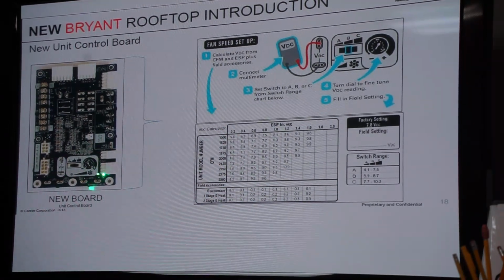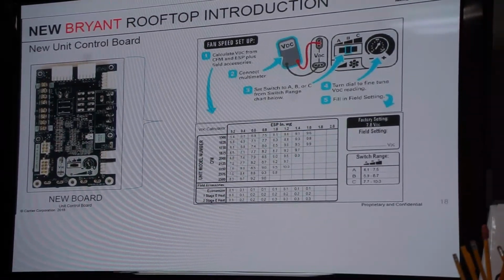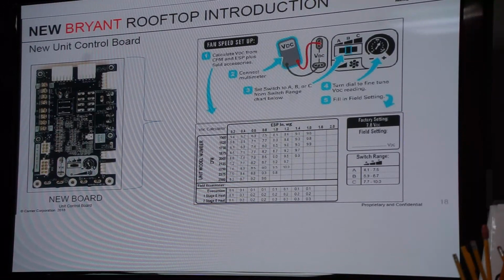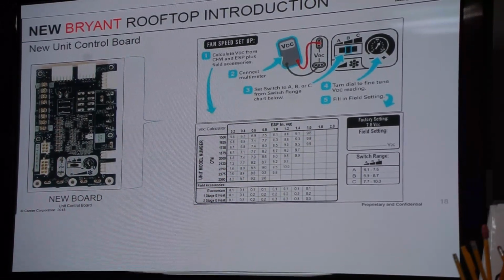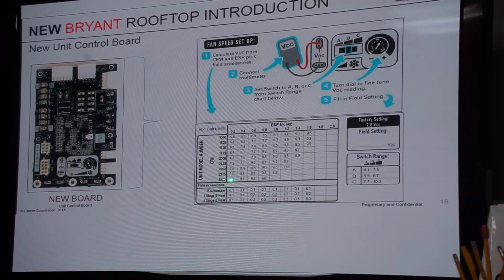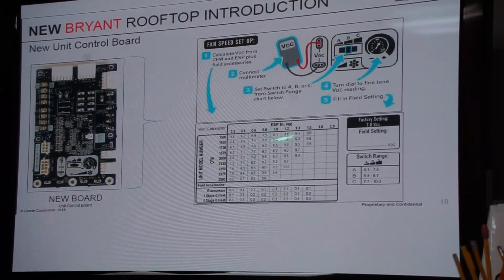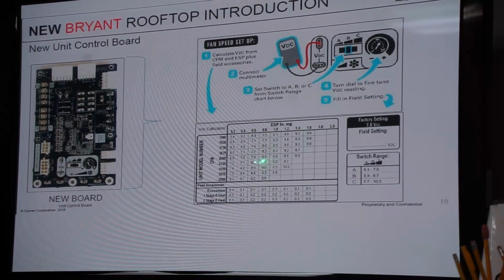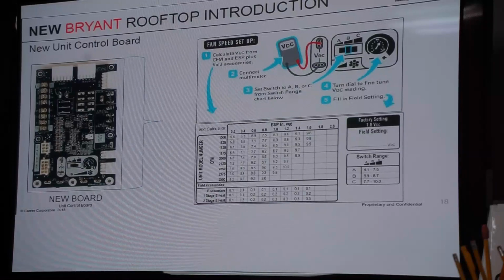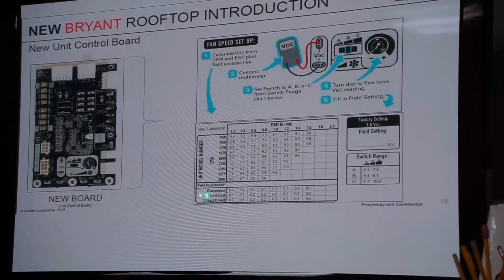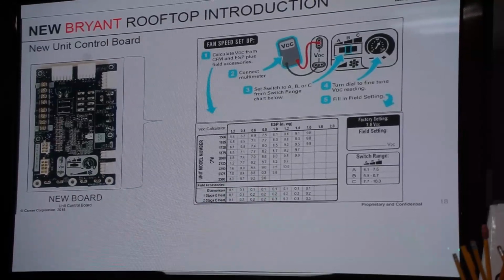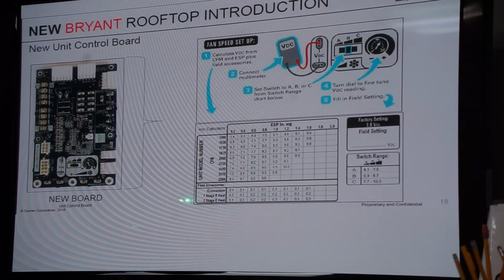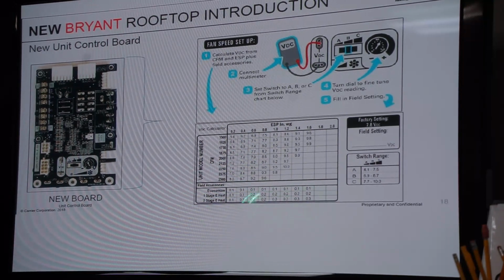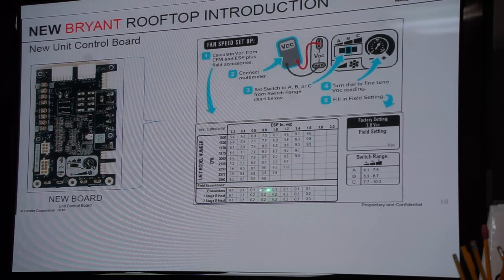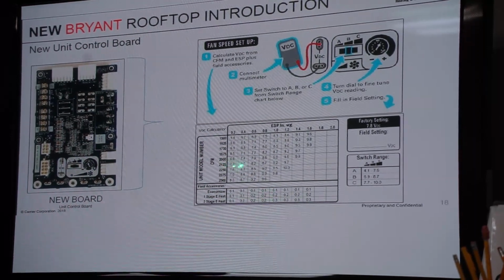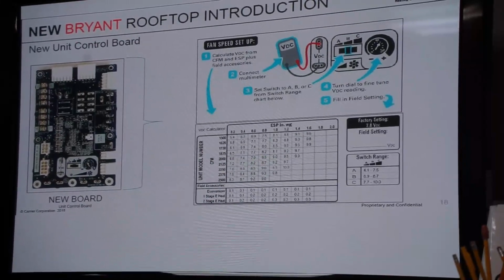We determine the voltage by this chart here, and that's going to be on every unit, ships with it, on the high voltage cover. But basically, if we want to set this unit up for 2000 CFM at 0.8 of an inch external, we're going to set this controller up for 8.5 volts. If I've got accessories on it, I'm adding voltage, not static. I've asked them to change that because it just says field accessories and then it gives you that, but that is actually voltage. So if I've got an economizer, I'm going to add 0.1 volts. So now my 8.5 has gone to 8.6.